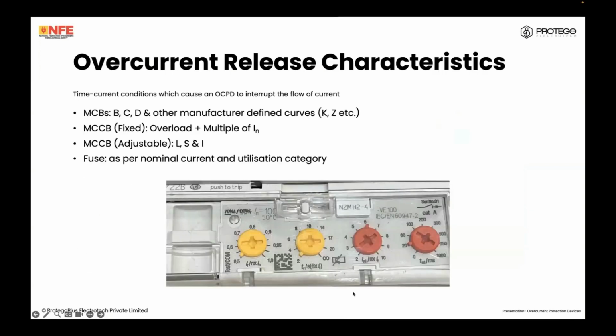Now, when it comes to overcurrent release characteristics, I'm sure those working in the heavy commercial and industrial sectors have seen these dials on our MCCBs. So these are basically the time current conditions which cause an overcurrent protection device to interrupt the flow of current. For an MCB, these are fixed: B, C, and D, and this is to 60898. For 60947 part 2 MCBs, these are manufacturer defined. Commonly you see K and Z. I'll show you the tripping curves in the next slide.